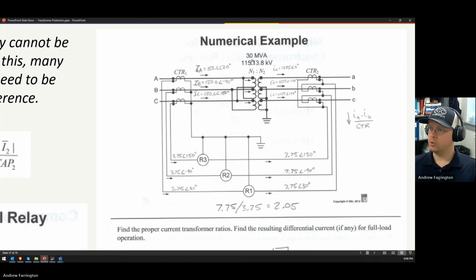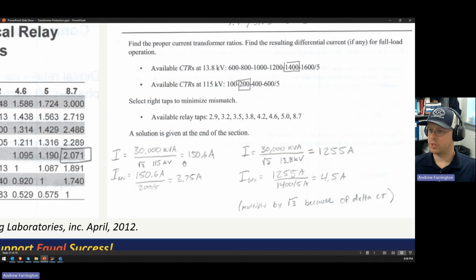And you calculate the phase current for the high side and the phase current for the low side. And those calculations are down here. So you take the 30 MVA divided by the square root of 3 times the high side phase-to-phase voltage rating, and you get 150.6 amps. And then what you want to do is select the CT ratio that is the next highest to that. That's to get above the thermal rating of the CT, right? You don't want the CT to get burned up due to load current.